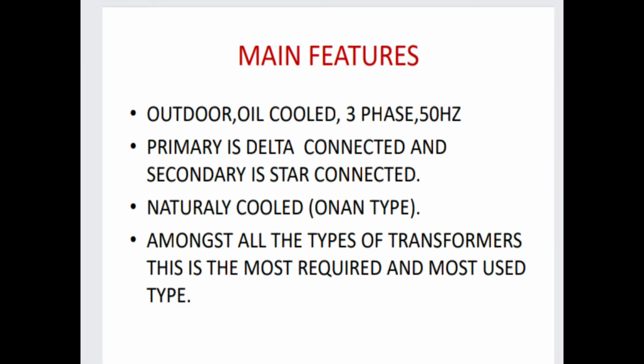So, main features of distribution transformer are: it is outdoor, it is oil cooled, and it is 3-phase 50 Hz. In this, primary is delta connected and secondary is star connected. Naturally cooled, ONAN type. ONAN means oil natural, air natural type. Amongst all the types of transformer, this is the most required and most used type. Means of all the types of transformer, distribution transformer is the most required and most used type.